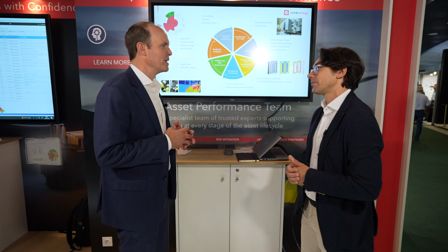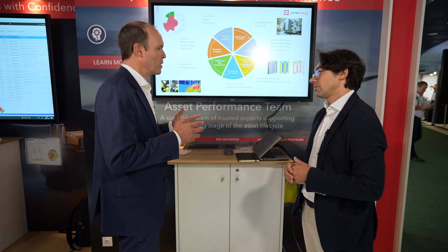And as far as actionable insights, if there's a scenario where the customer has an alarm or some data they're unsure about, tell me more about your technical services. Yes, this is becoming more and more usual now - together with the monitors, getting 3-5 years of support services to make sure alarms are under control, because every transformer is different. You can't set the same alarms for every transformer.